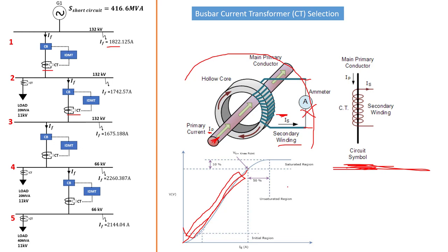We know that the output current IS is following what the input current is doing — it's linear. But when the output current stops following the input current, we reach the saturation region. We're no longer in the linear zone or the good zone — we're in the danger zone. Why is it a danger zone? Because it doesn't matter what that current is now; the output will no longer give an accurate representation. We could be having 100 million amps there and this secondary IS will not tell us what exactly that current is. So protection is lost — you don't have your protection anymore.